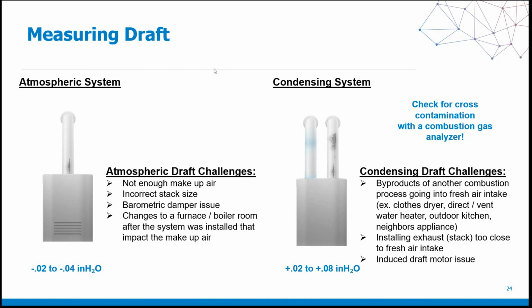Also, when we talk about a condensing system, we need to talk about cross-contamination. Most people are not aware that a combustion analyzer can check for it. And it can. Because a combustion analyzer has 7 tools. It does your combustion analysis, yes. It's an ambient CO monitor, which I just went over. It's an ambient temperature monitor. It measures draft. It measures efficiency. It measures pressure, cracked heat exchanger, and it also checks for cross-contamination.